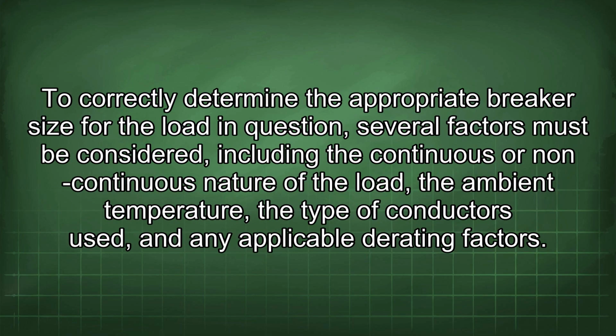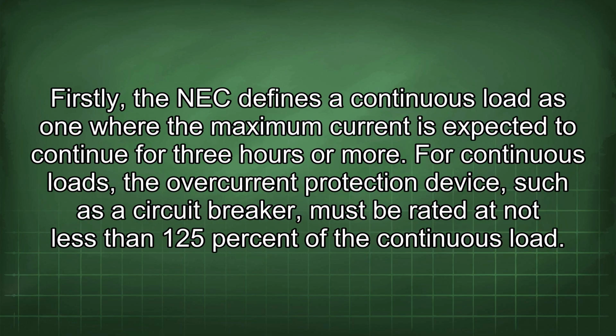To correctly determine the appropriate breaker size for the load in question, several factors must be considered, including the continuous or non-continuous nature of the load, the ambient temperature, the type of conductors used, and any applicable derating factors. Firstly, the NEC defines a continuous load as one where the maximum current is expected to continue for 3 hours or more. For continuous loads, the overcurrent protection device, such as a circuit breaker, must be rated at not less than 125% of the continuous load.